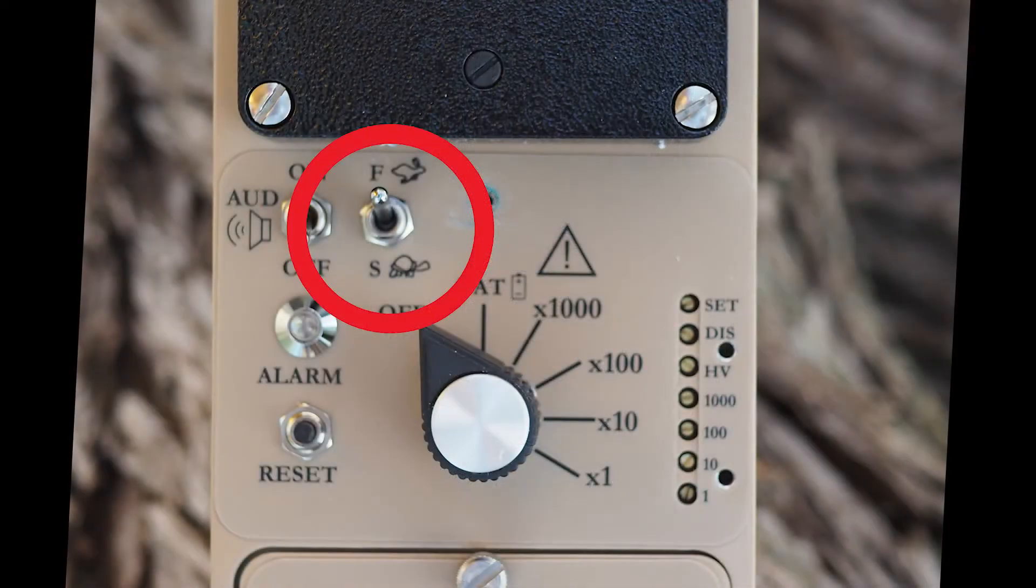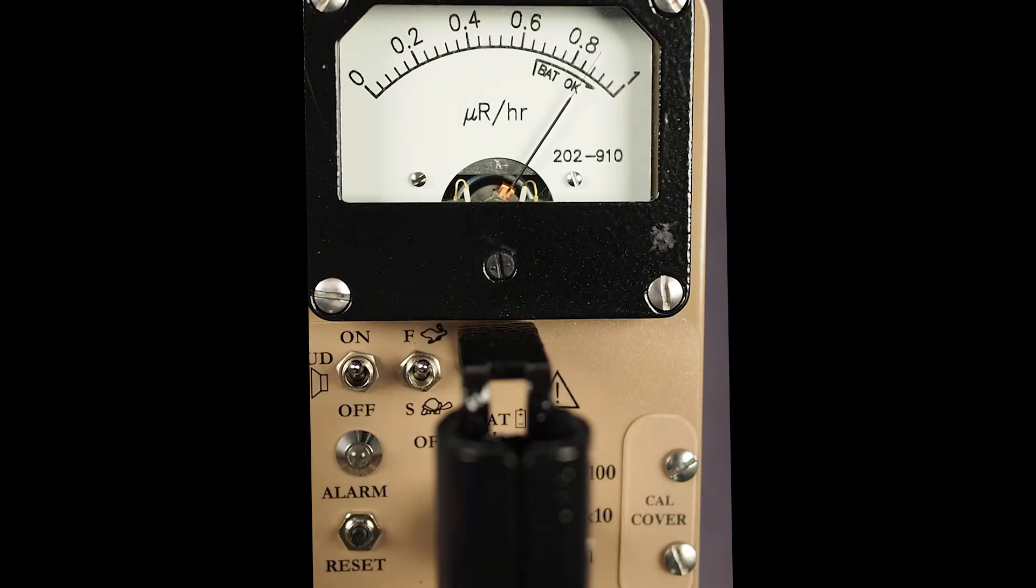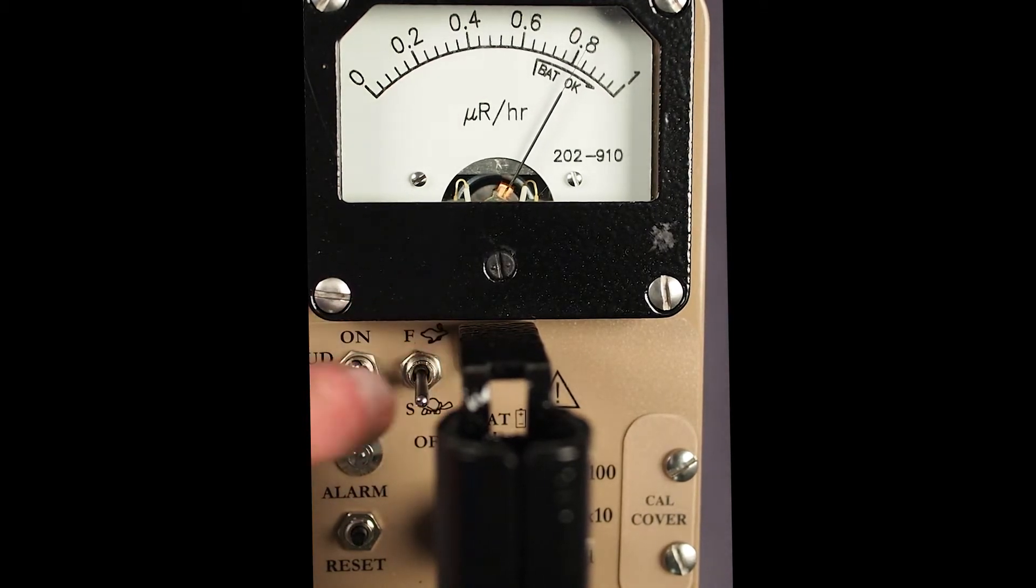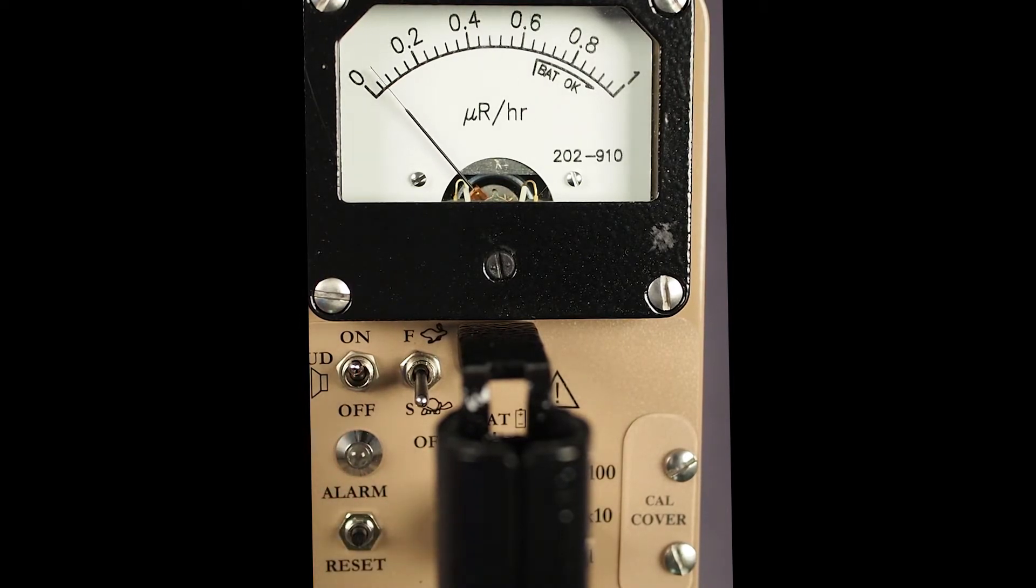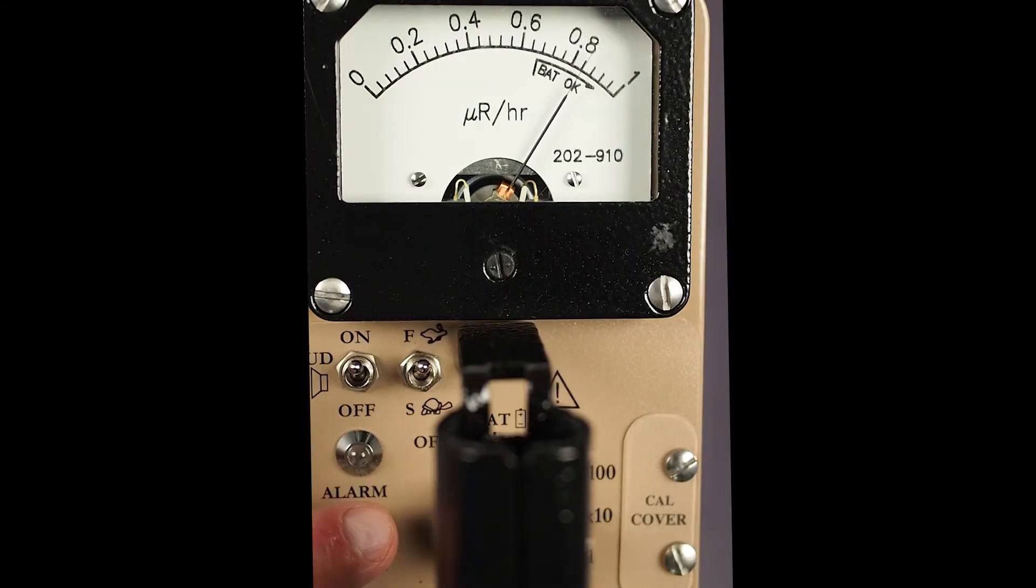The F-S toggle switch determines the meter response time. Selecting the fast, F position of the toggle switch provides 90% of full-scale meter deflection in approximately 4 seconds. In the slow, S position, 90% of full-scale meter deflection takes approximately 22 seconds. In most circumstances, the model 193-6 should be used with the switch in the F or fast position.